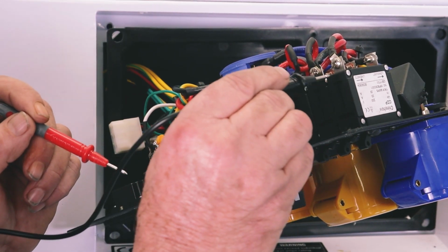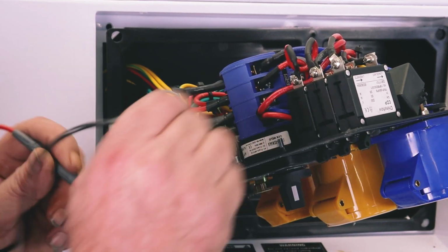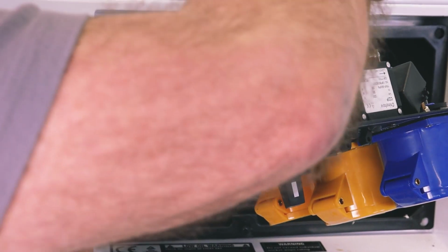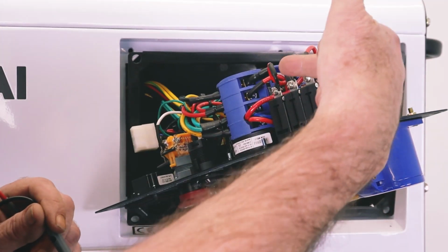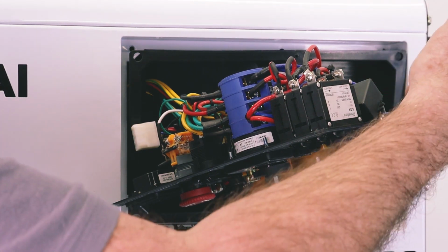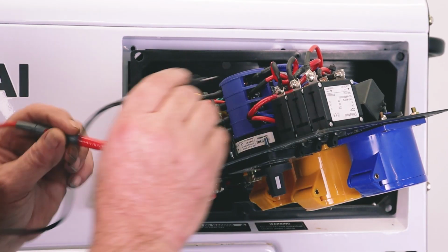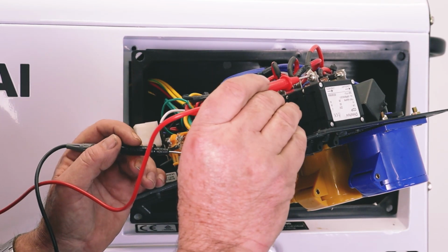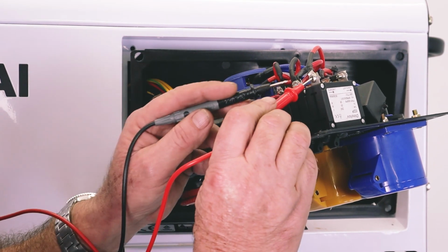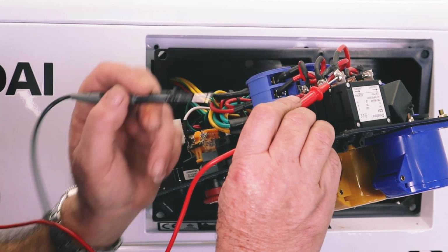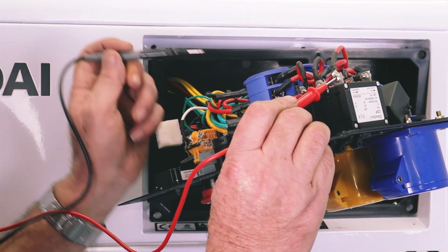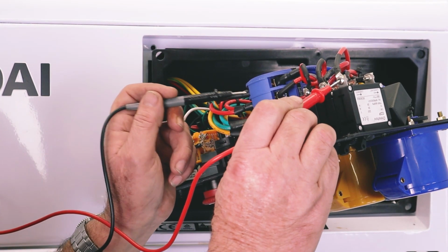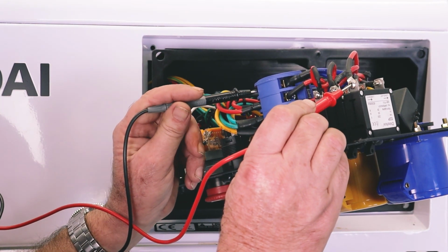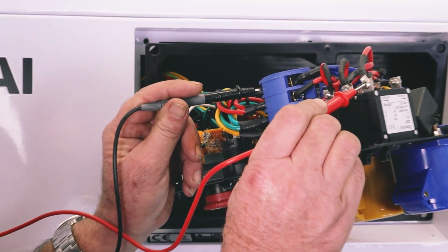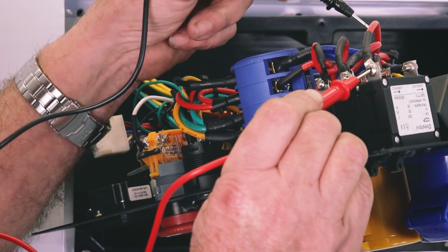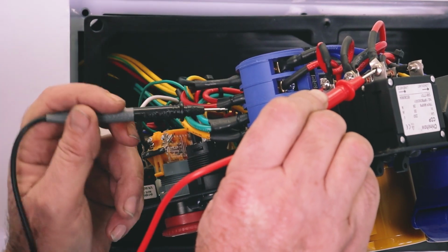Let's have a look if we're getting voltage to the circuit breaker for the 230. Now the positive from the changeover switch comes in on this wire, which is normally the top of the panel, out on the bottom. So we need to see, we can probe here. If we just put the probe on there, that's 230 positive, or should be, because it's not passed through the switch yet. And if I go to any one of the negatives on here, so I'm going to go to the black one, check for voltage. If I get nothing, that pretty much tells me that there's a problem within this wire to the changeover switch.